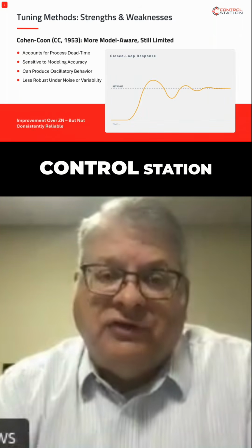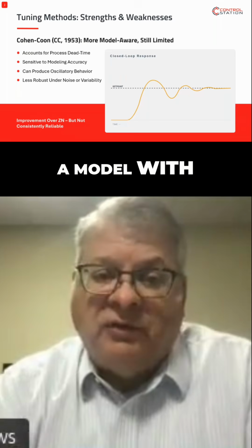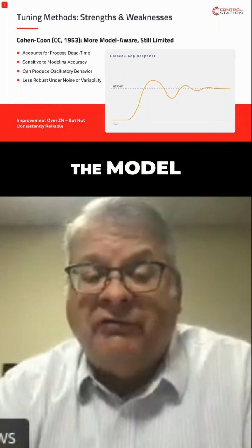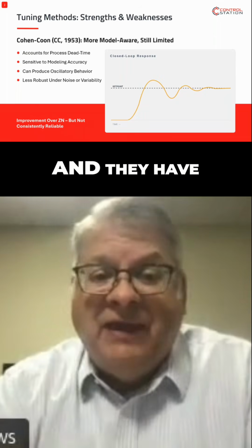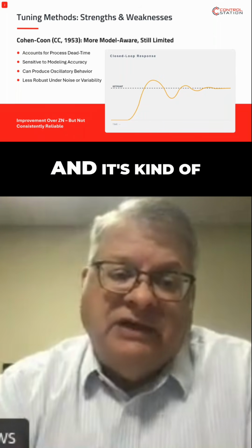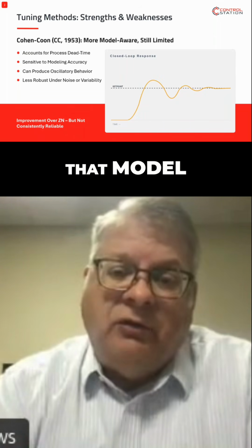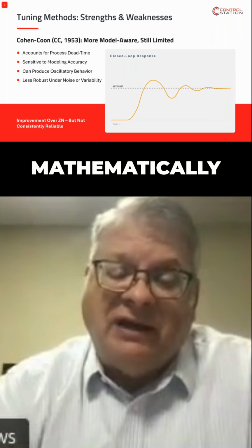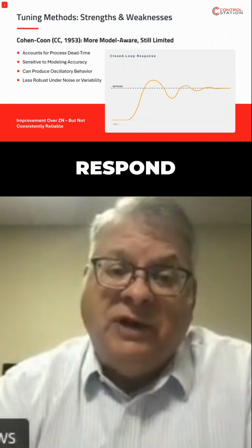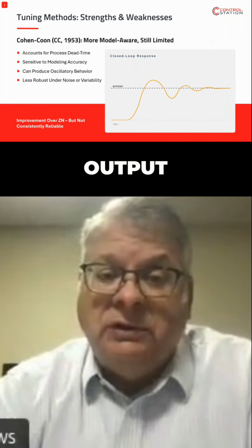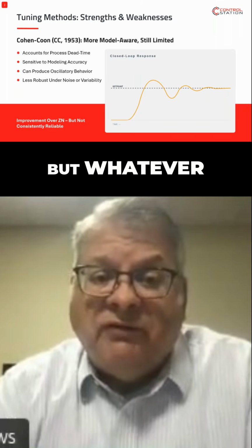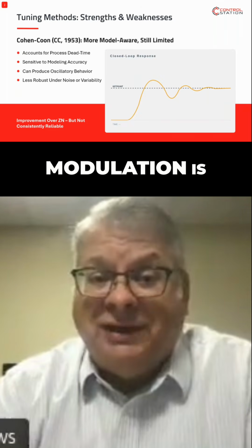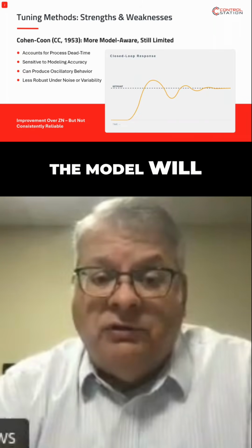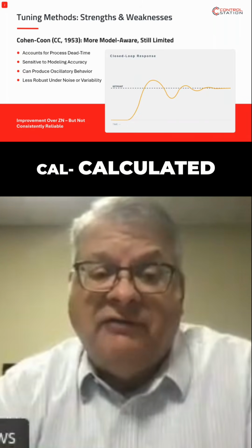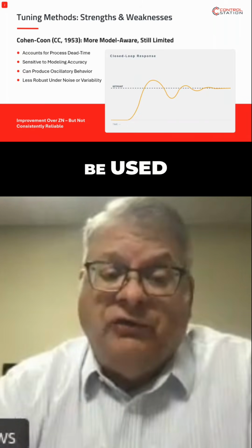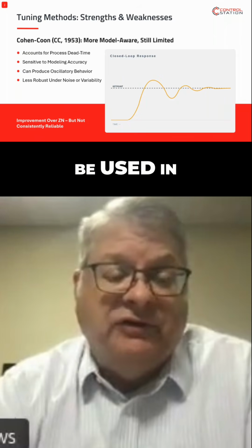Now, something that Control Station teaches is to use a model with your process, which means you need to determine the model from the process you're going to tune, and they have a method to do that. And it's kind of good because that model would accurately describe mathematically how your process does respond whenever you have changes in your control output. It could be a valve or a VFD, but whatever the control output modulation is, you can see that the model will be able to be calculated, if you will, some parameters that could be used. Now, those parameters then can be used in Cohen-Coon.